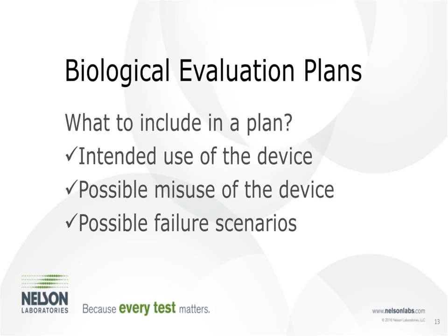You know, all these questions need to go into as far as the intended use of the device. The next thing we have to look for is possible misuse. Will this device be used with your knowledge in a way that you did not expect it to or intend it to, or maybe just didn't put in your IFU because you didn't want to evaluate it? We have to look at that possible misuse of that device and the impact of that. Remember, we're looking at all the risks. And we talked about failure scenarios. Devices fail. Pieces fall into surgical sites. Balloons burst. These things happen. We deal with them every day.